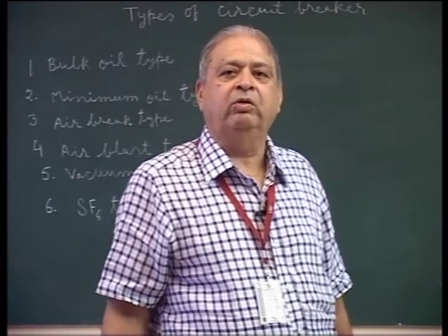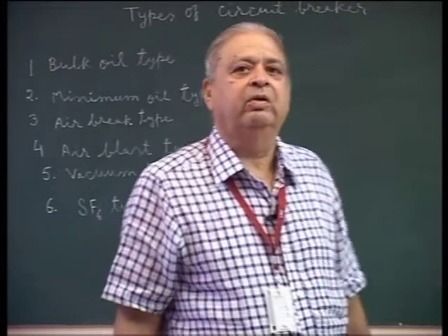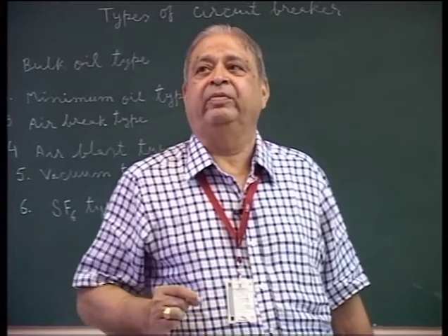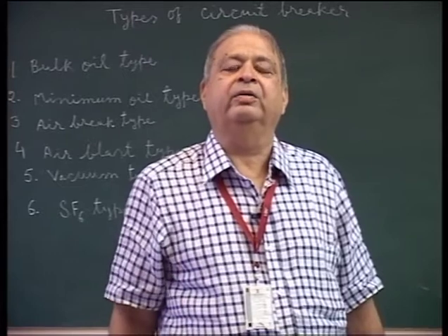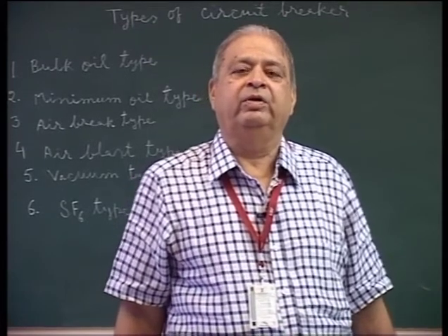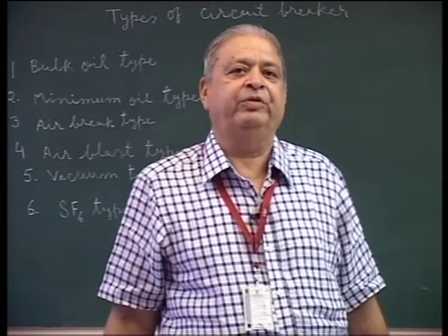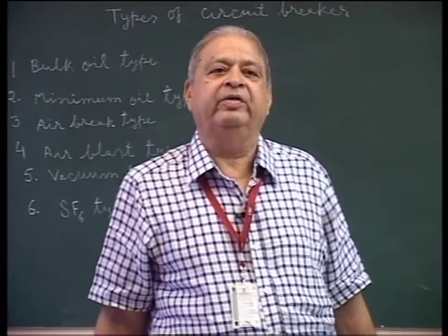This is a very strong circuit breaker. The air is thrown only for a very short duration, just for less than a second, and the arc is blown out. There is a violent sound created due to operation of the circuit breaker because of high pressure air injected on it.